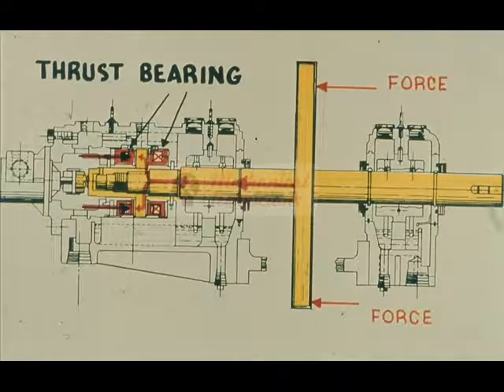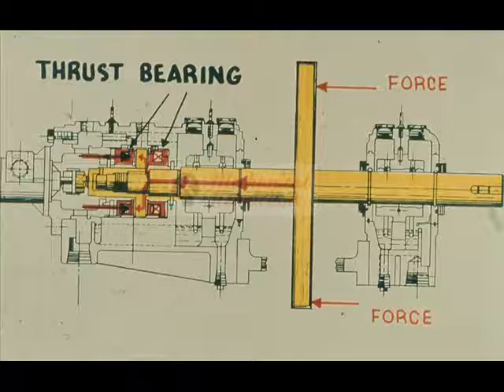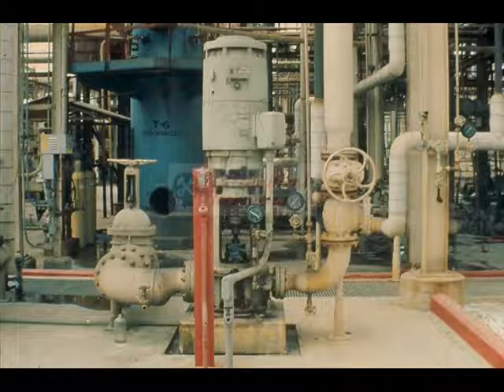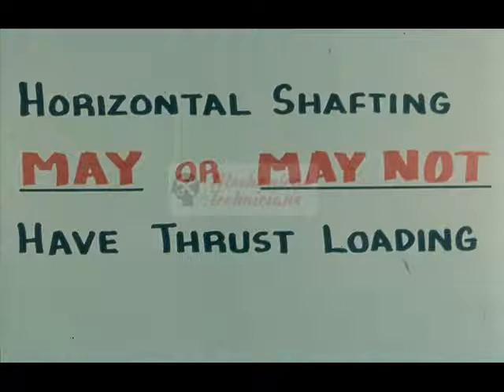The position of the rotating shaft within the machine must be maintained by thrust bearings exerting an equal but opposite force upon a thrust collar locked to the shaft. In machines with vertical shafting, axial loads are more or less always encountered and are usually in one direction only. In addition to forces caused by liquid and gas pressures, the weight of the rotating assembly itself must be supported. In machines with horizontal shafting, axial loads may or may not be encountered.